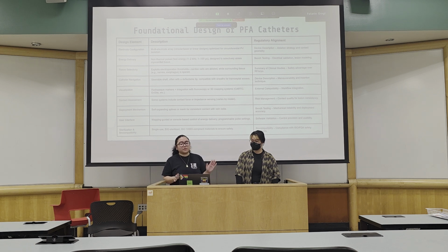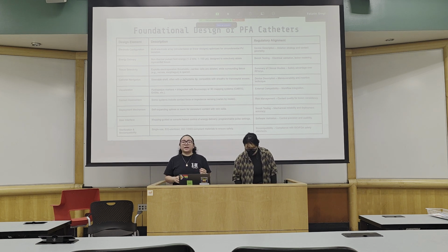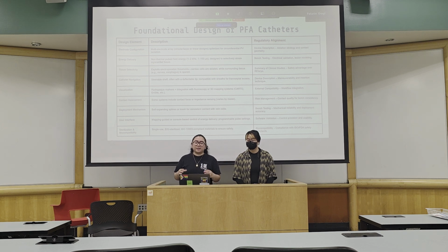And then for all of the design elements, there's also the energy delivery. So basically how exactly the pulse field energy is administered during the procedure, and how it's supposed to specifically ablate myocardial tissue. That's a key component for PFA catheters especially. And that would go into bench testing from what we're going to see with regulatory alignment, just making sure you're able to go through the correct electrical testing and making sure that it's not giving out too strong a voltage that it could damage surrounding tissue, but it's giving the right amount to ablate the affected tissue.